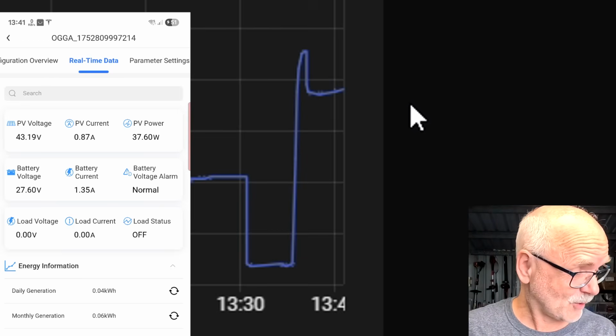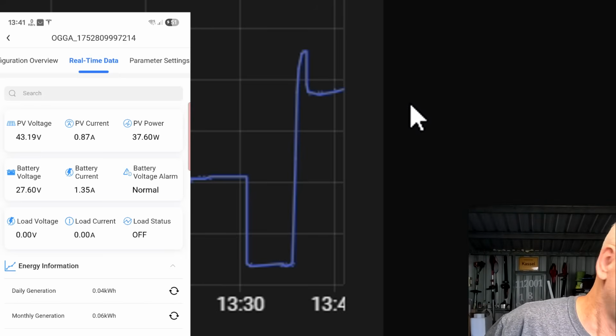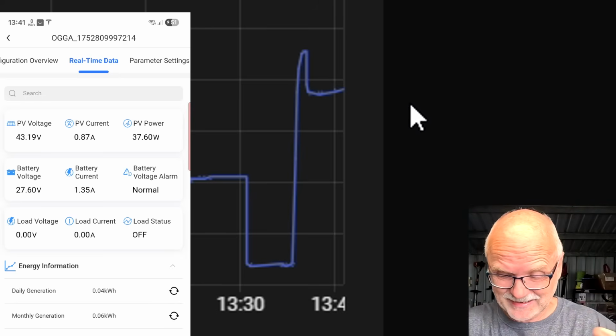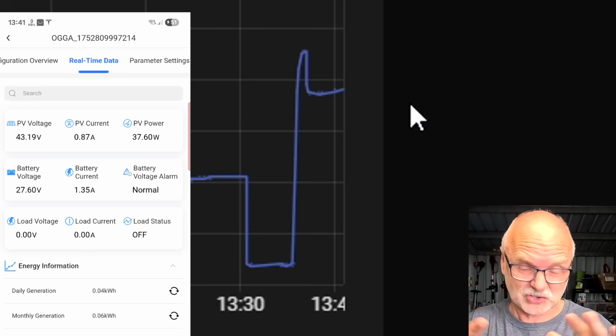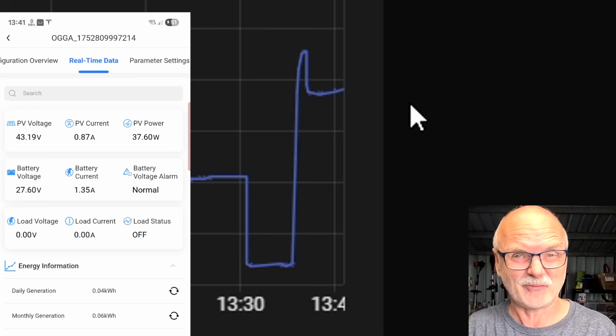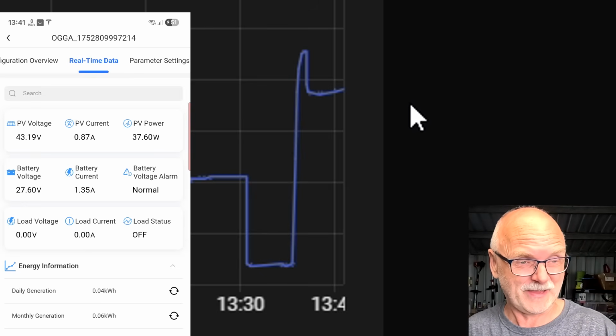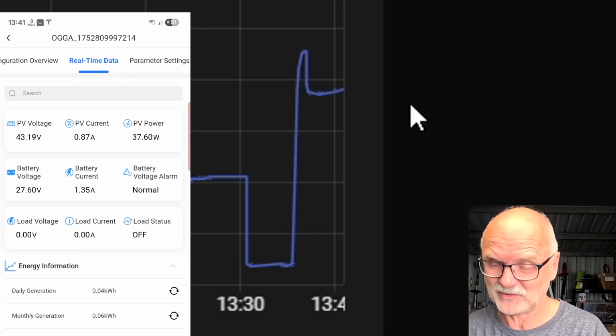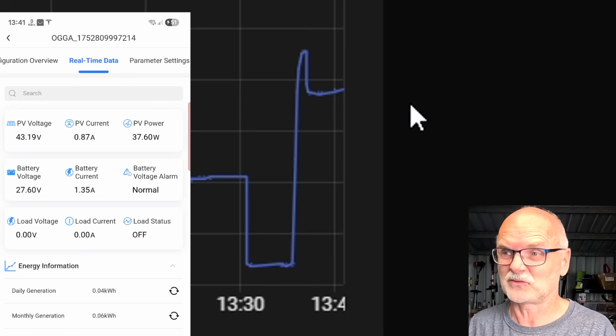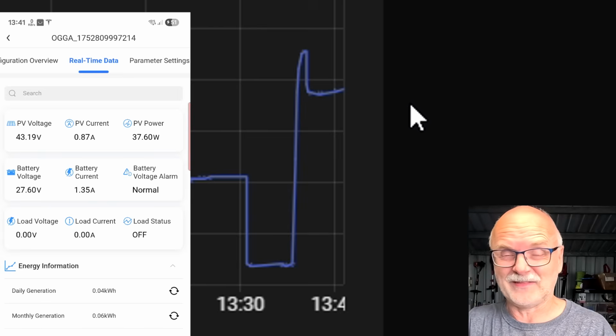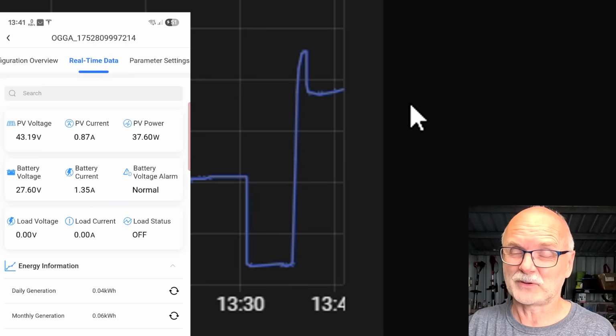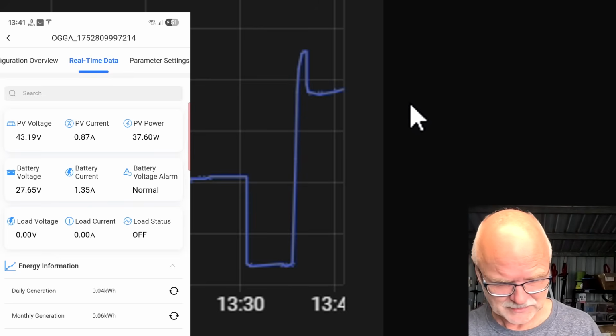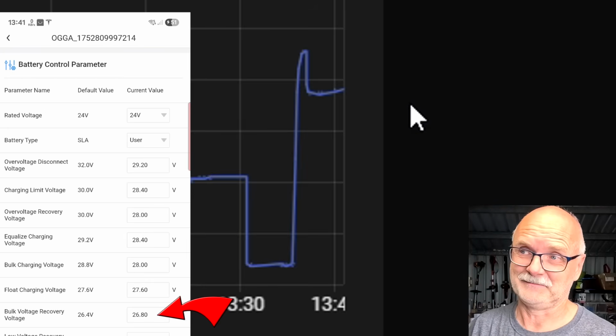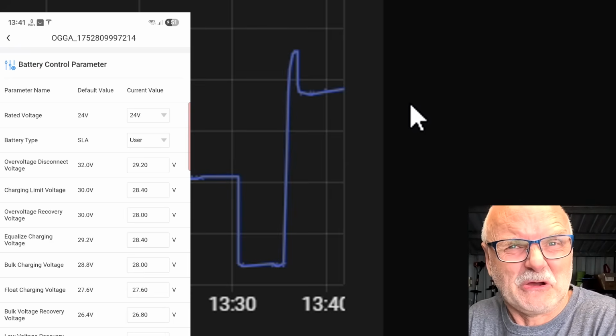I'm going for lunch now for the next 20 minutes or so, and we'll leave this all sitting here on float voltage, let the battery float and still absorb at 27.6 volts, what the Solar Charge controller thinks it is. Then we'll have another look at the curve and do a discharge test, and set the absorption time a bit longer, because to trigger another absorption voltage now, we need to go under 26.8 exactly. All right, and I also need to go in the sun - it is so cold in here.